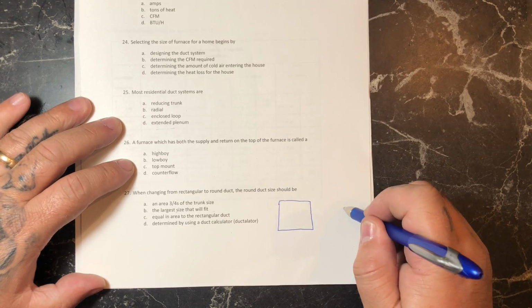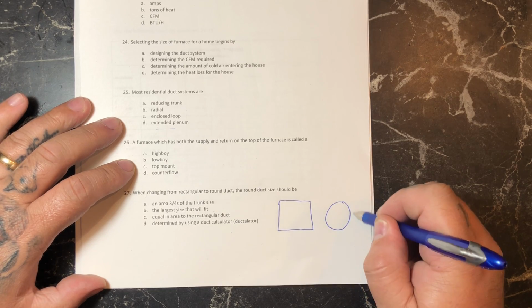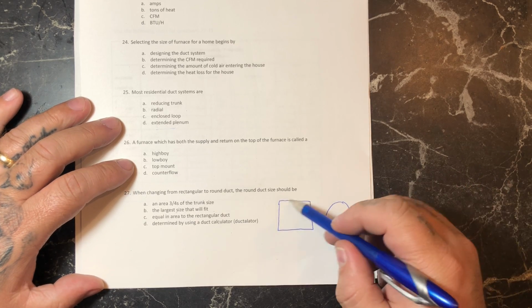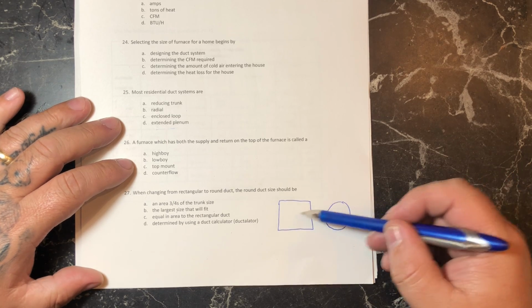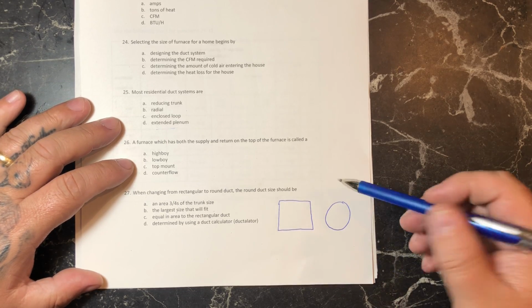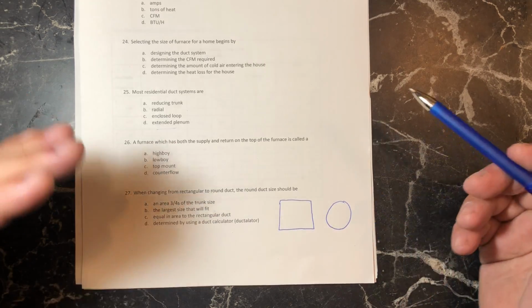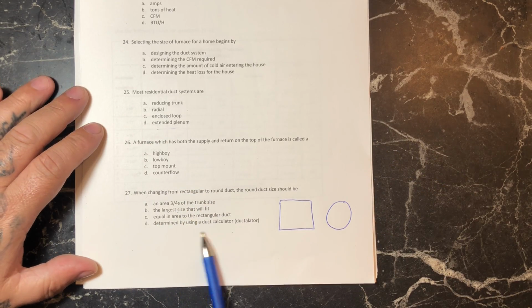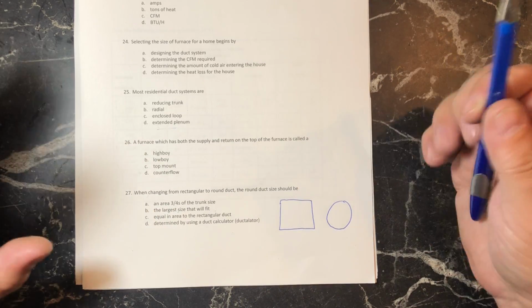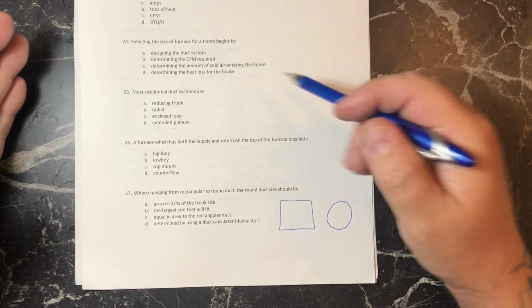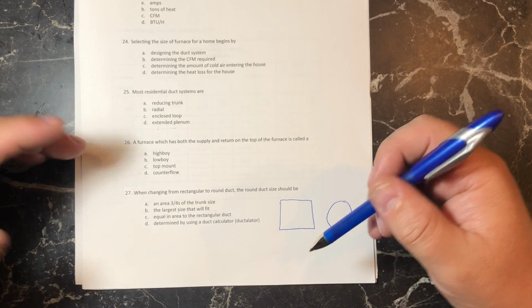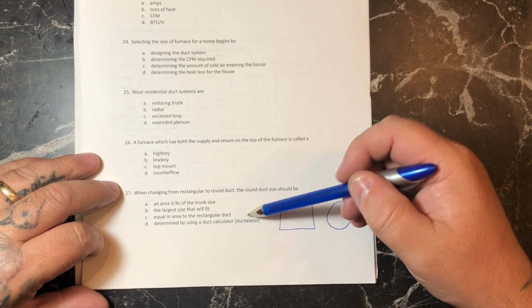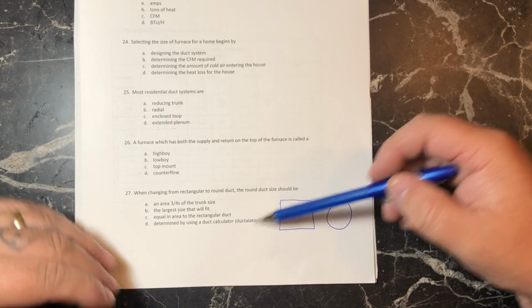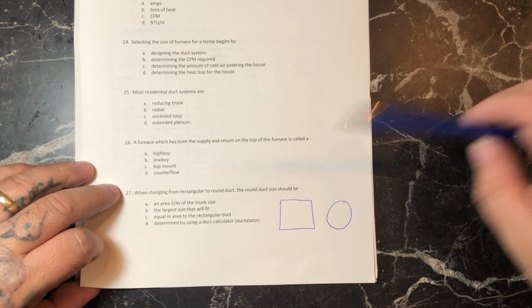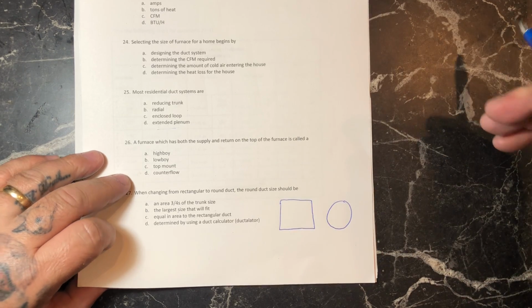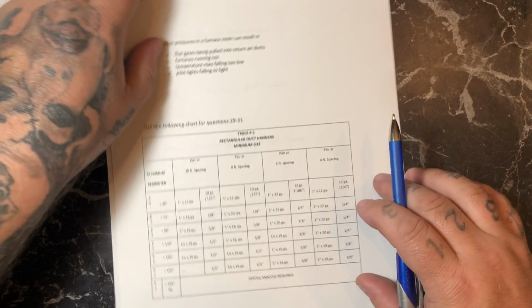If I have a round duct, the perimeter or circumference of that round duct is going to be less than an equal area size square duct or rectangular duct. So to find out the proper equivalent size, I'm going to be using a ductulator. It's a sliding scale ruler, designed way back when by a sheet metal worker, that will determine what that equivalent round size would be for the square size. All right, moving on.